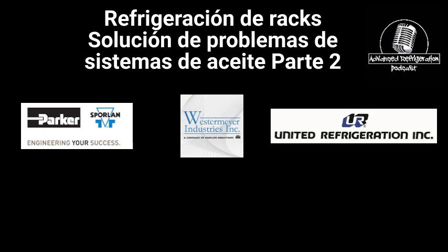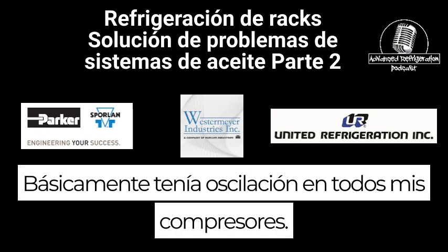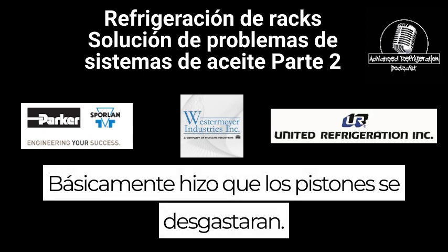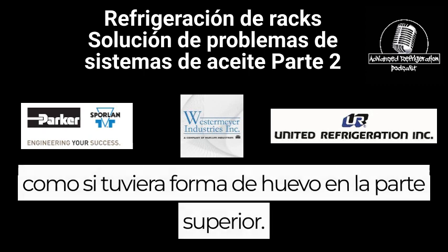Basically, I had copper plating in all my compressors. I had moisture in the system that caused bearing wear on the main crank, in the main journal. It basically caused the pistons to wear funny. I have some pictures where it actually looks egg shaped at the top.